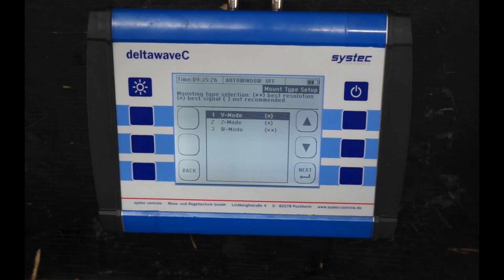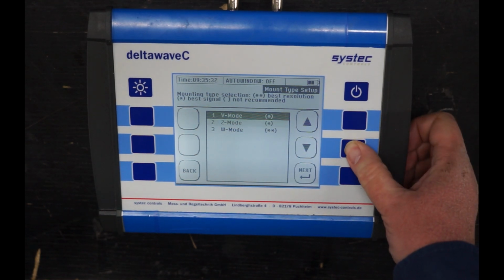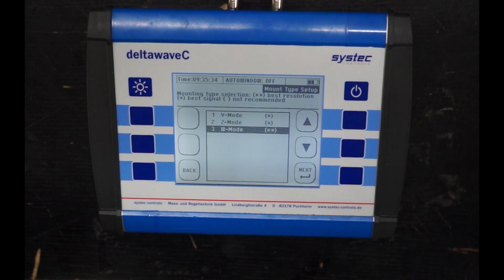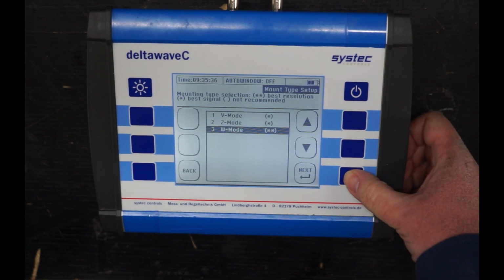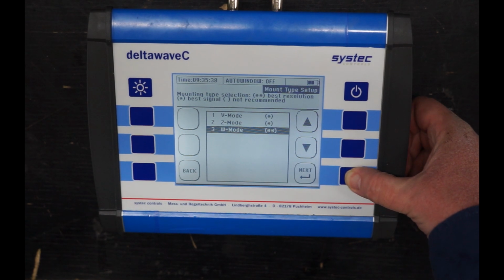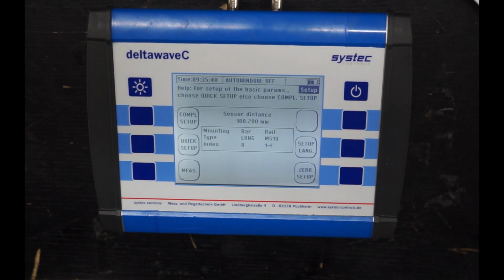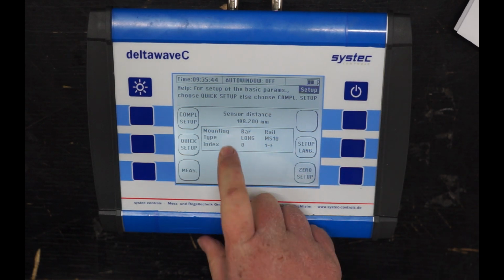Finally, you need to choose the transducer arrangement for your application. The mode will define the number of path reflections in the pipe and the path length. A longer path will give you more precise results, while a short path will have less disturbance in the signal. The device will also give you a suggestion on what mode will work best for your application. In our case, I will select the 2-star suggested W mode. With these simple steps, the quick setup is complete.